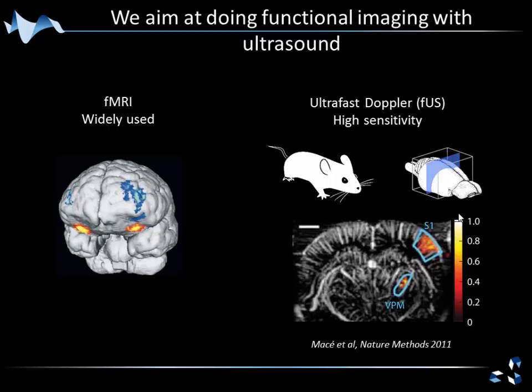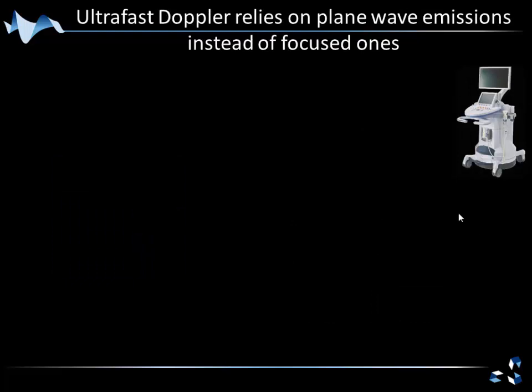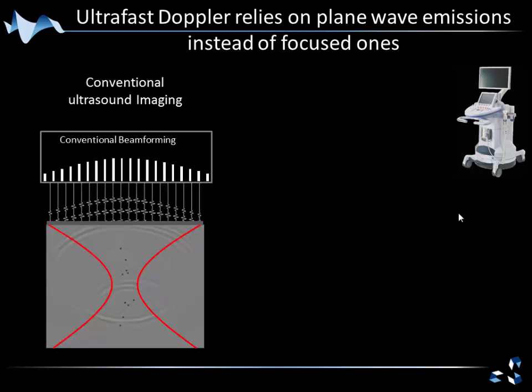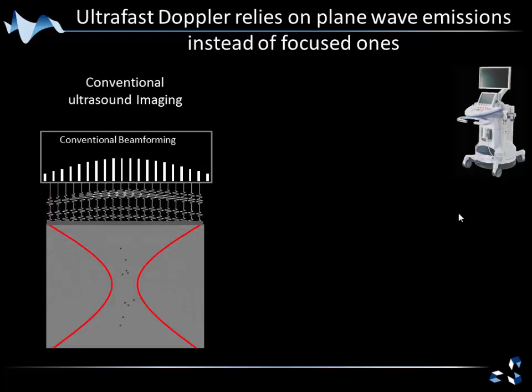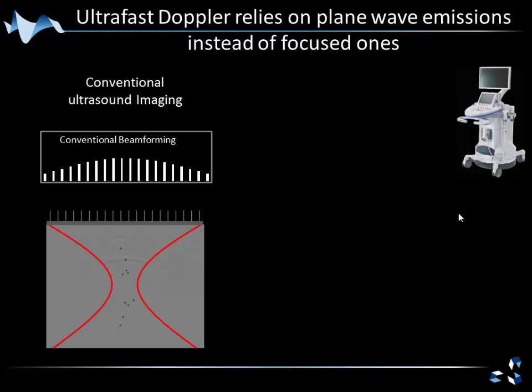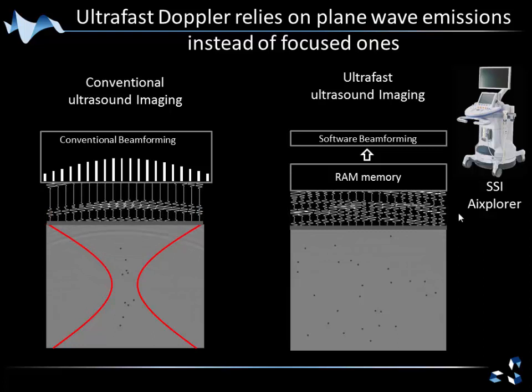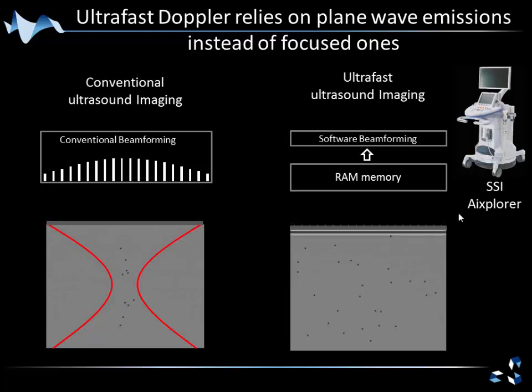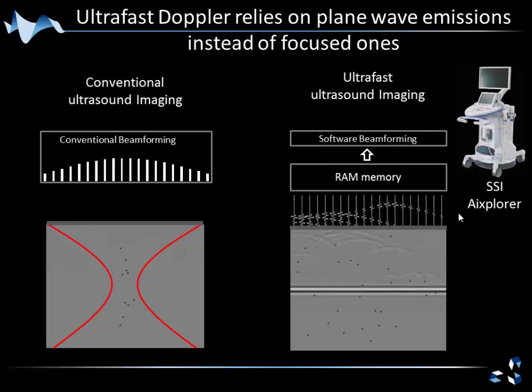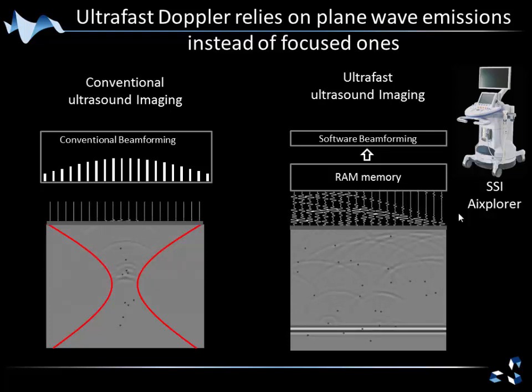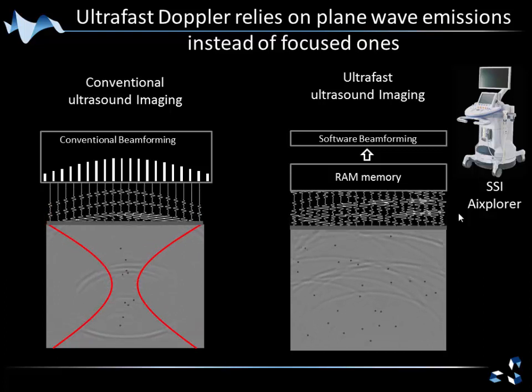This is what I'm going to talk about with this special filter. To explain the difference between ultra-fast Doppler and conventional Doppler: in conventional Doppler, you send a focused wave inside the medium and build the image line by line, requiring about 100 emission-reception processes to build a complete image. Whereas in ultra-fast ultrasound imaging, you send a plane wave, record all echoes at once, and build images continuously. The gain in speed is more or less a factor of 100.